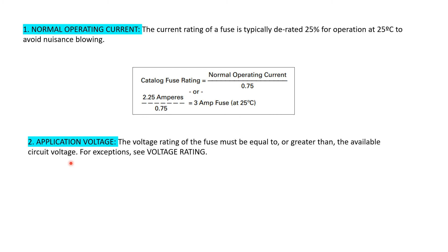If it is more critical, you have to understand that, and you can still put it closer, like 30% or something like that. But my recommendation is you must derate 25% of the normal operating current. Then application voltage. Whichever circuitry you are going to put the fuse in, the voltage rating of the fuse must be equal to or greater than the available circuit voltage. There is not much derating factor required here. You can select equal to or a little bit greater than that, and it is okay.